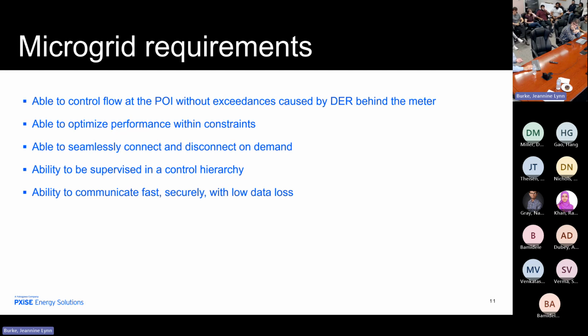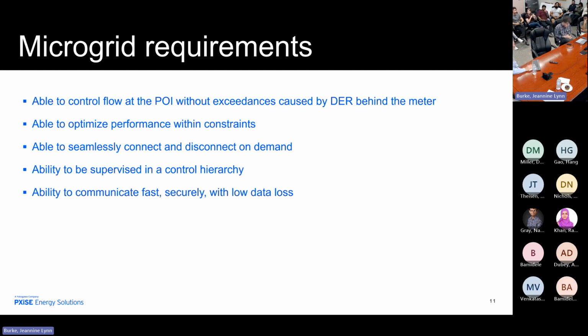Now, we've mentioned that we have to control the flow. We have to optimize the flow because why would people buy a microgrid in the first place? They want to reduce their power bill or make money. That means they have to have an optimizer. So a microgrid needs a built-in optimizer to figure out if I am participating in the market, what am I going to bid into the market in terms of P and Q at a specific time and keep my battery full. Because if my battery runs out, I've lost control authority. That's another thing that a lot of people sort of ignore. How do you control the battery profile to allow you to get optimal control of the POI, at the flow point, at the point of interconnection?